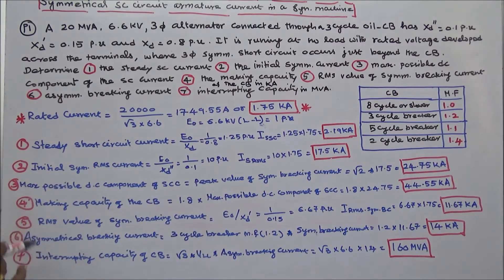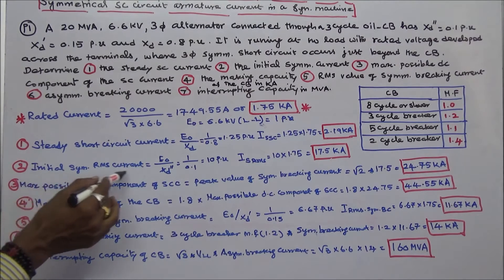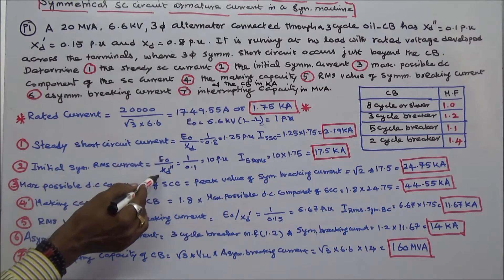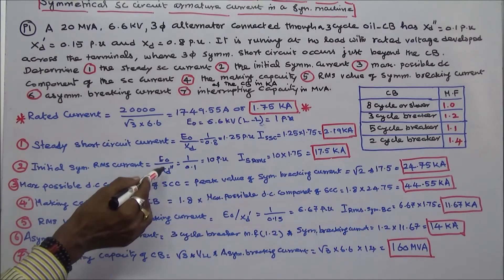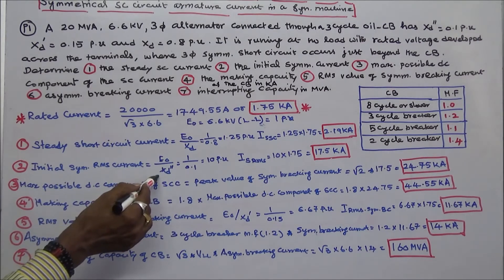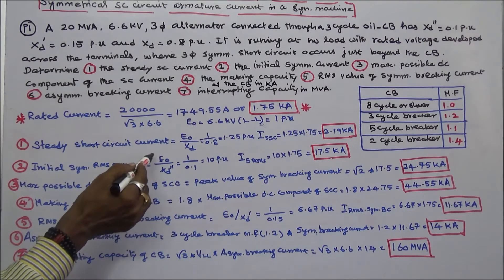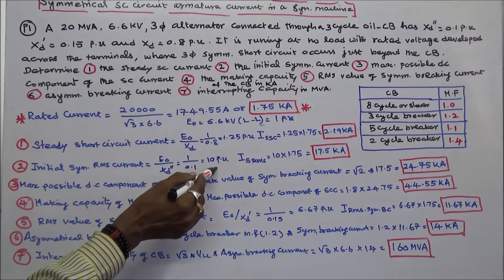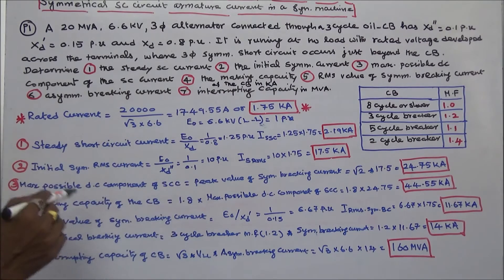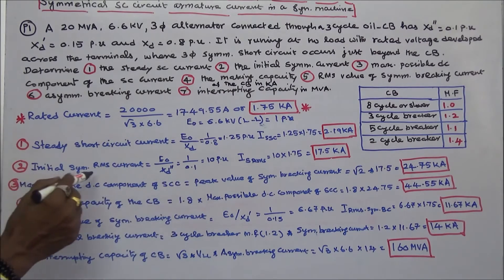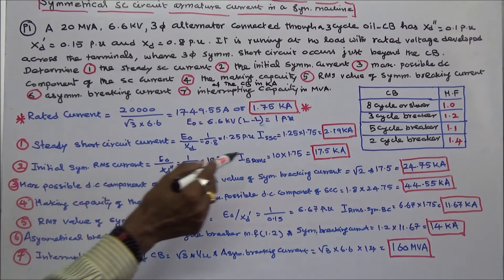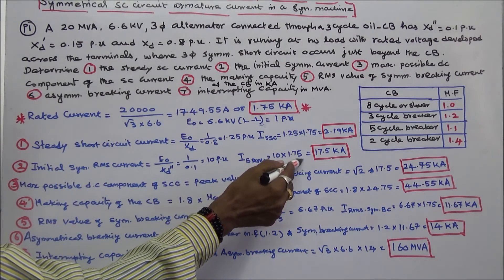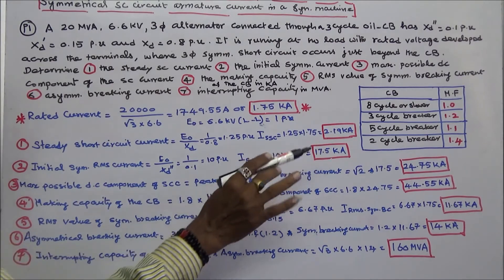Second is the initial symmetrical RMS current. That equals E0 divided by subtransient reactance. Subtransient reactance is 0.1, E0 is 1, so 1 divided by 0.1 equals 10 per unit. Actual initial symmetrical RMS current is 10 into 1.75, which equals 17.5 kA.